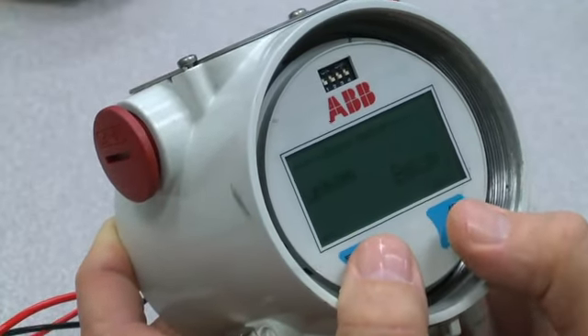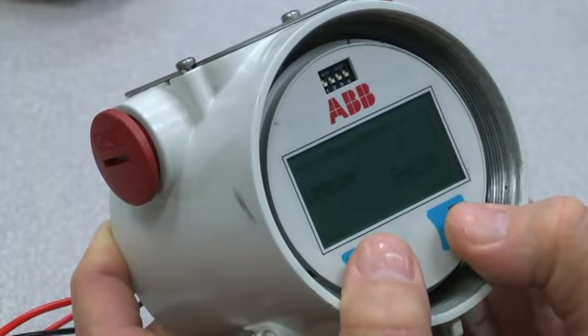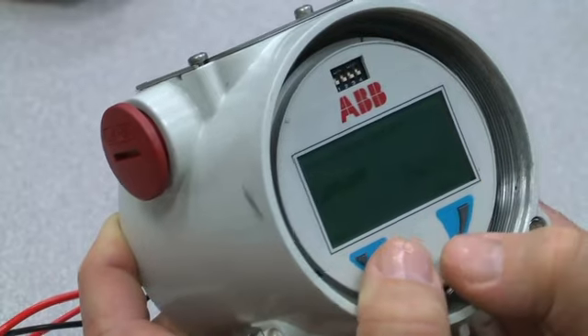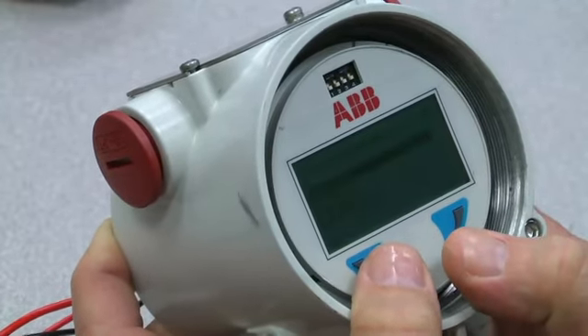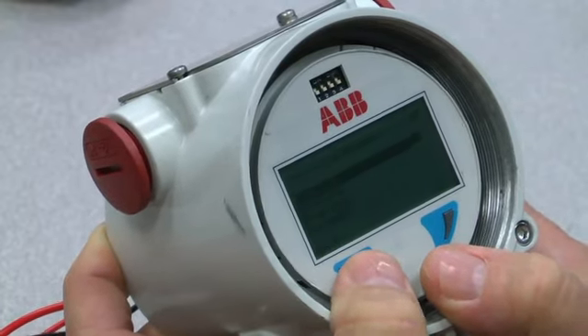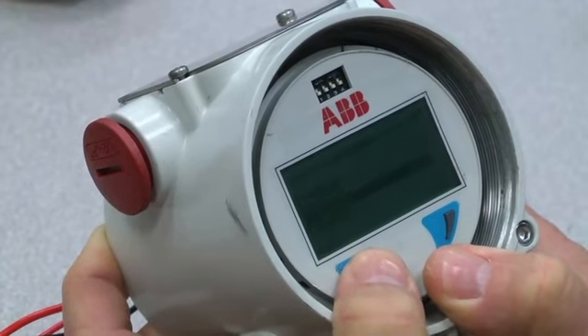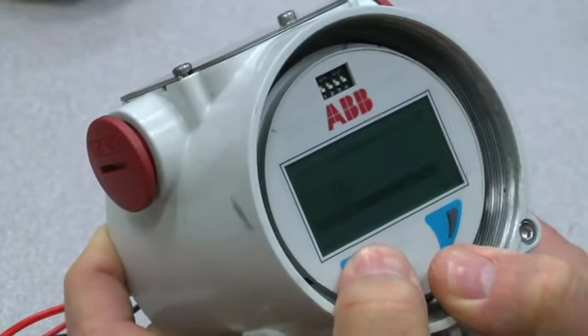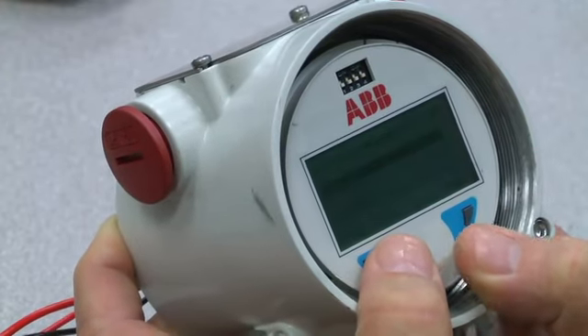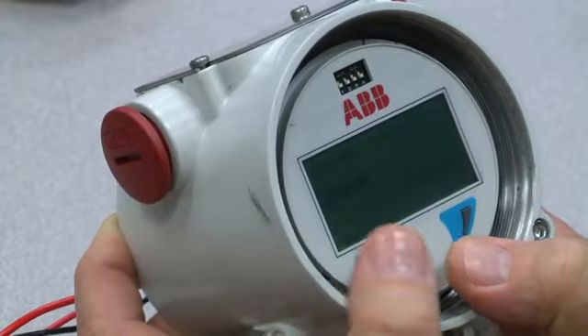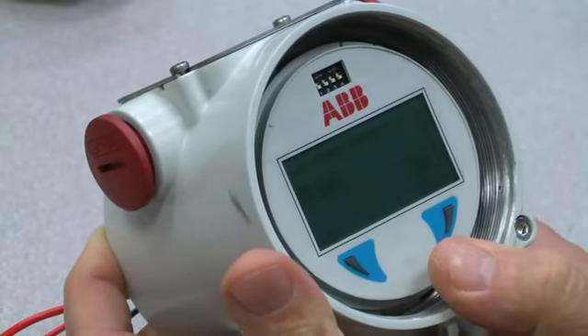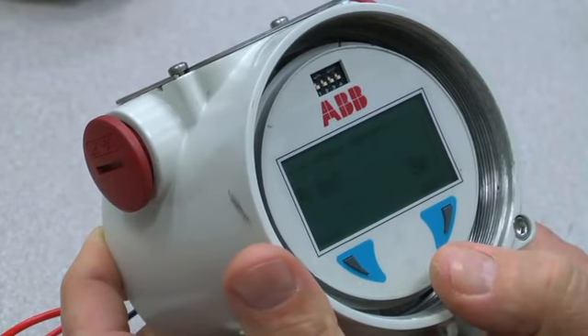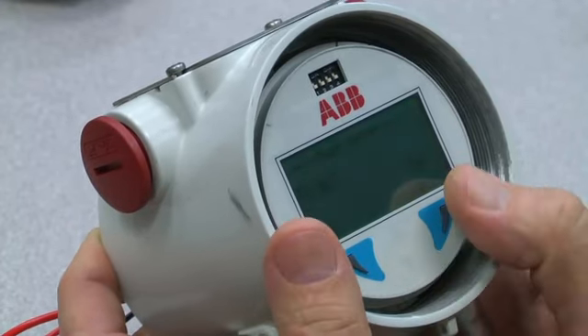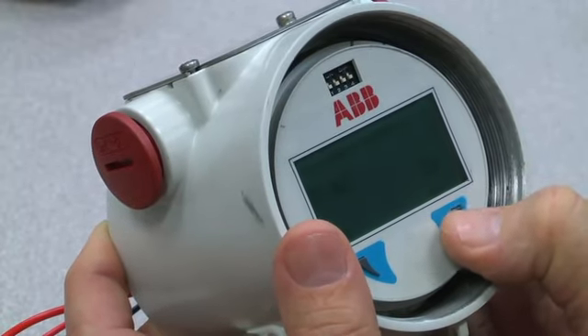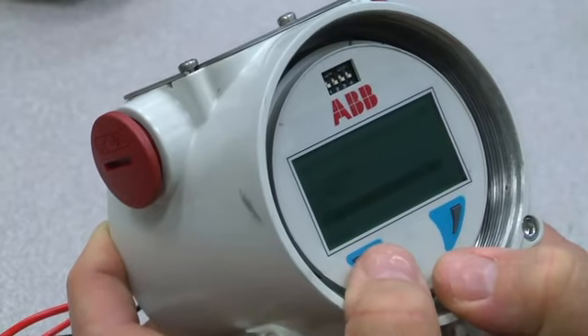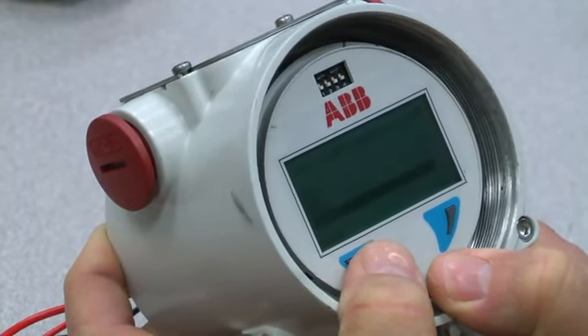And this is where I can set my language. Most of these are going to be defaulted to the correct settings, but there may be some that you want to edit. If I wanted to edit, I'd select edit, and then the Z button turns to next. So now I can go through each of those items and scroll through until I reach the one that I want to use. I'm just going to go back to English, select it, say OK, and now I'm going to go next in the menu, and this is going to be the PV unit or the process variable unit. Right now it's set on bar, so I changed that one on purpose so I could edit it for you. I'm going to set it to PSI, so I'm going to scroll through with the next button.